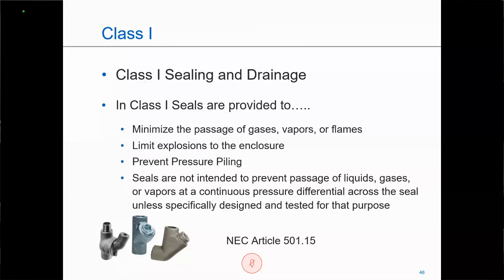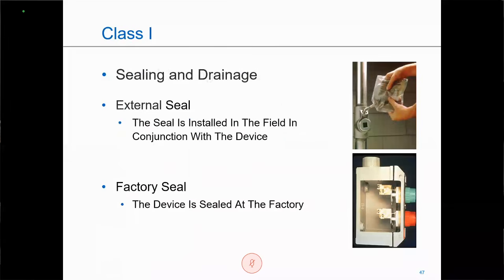In other words, if you were to put water on top of the sealing fitting, sooner or later it's going to migrate down through the fitting. And where this becomes important is in process seal applications, and that's covered under Article 501.17 of the National Electrical Code. But for today, we're really going to be focusing on more of the standard applications for sealing and not that process seal or secondary process seal application.